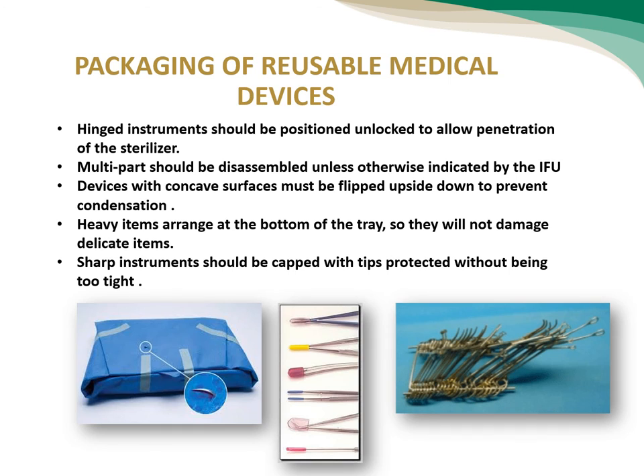Packaging of reusable medical devices. The hinged instrument should be positioned unlocked to allow penetration of the sterilant. Also, multiple parts should be disassembled unless otherwise indicated by the instructions for use. Devices with a concave surface must be flipped upside down to prevent condensation. Also, the heavy items are arranged at the bottom of the tray so they will not damage the delicate items. Sharp instruments should be capped with tips protected without being so tight.